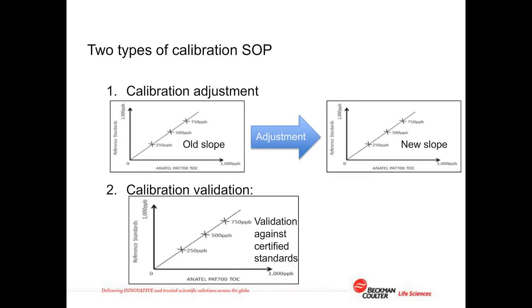There are two types of calibration. The International Standards Organization, ISO, defines calibration as a validation of an instrument against a known certified calibration standard. If the measurement error is not acceptable when compared to these standards, then a calibration adjustment must be undertaken to adjust the instrument's calibration slope to bring its performance within acceptable tolerances.